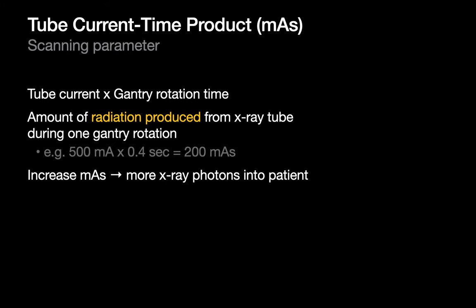X-ray tube current and gantry rotation time are often linked and referred to by their product, the tube current time product, or by its units MAS (milliamp seconds). MAS effectively quantifies the amount of radiation produced by the x-ray tube during one rotation of the gantry. Increase the MAS and you're effectively increasing the amount of x-ray photons you're shooting at your patient.